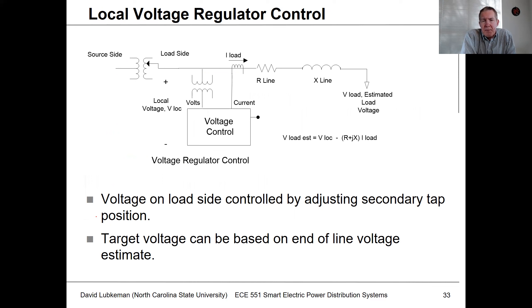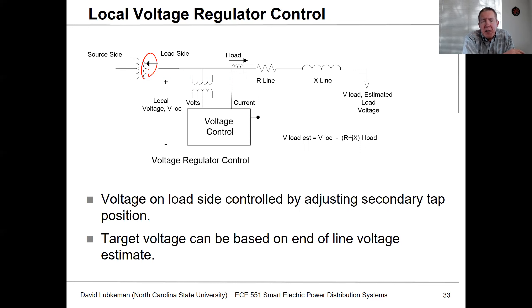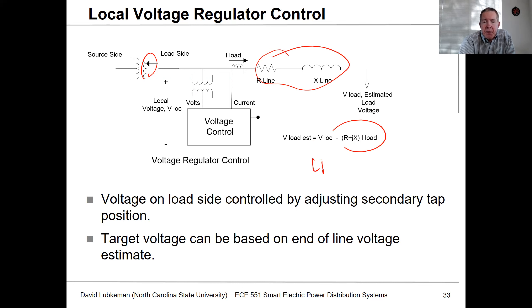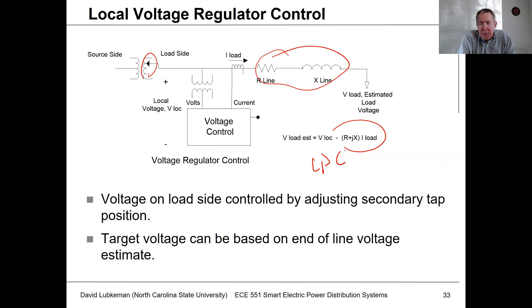Comparing this with line voltage regulators, the line voltage regulator has more resolution in terms of taps — about five-eighths percent resolution per tap. If you really wanted to fine-tune voltage control, a line regulator would be the way to go. If it's placed upstream of a load separated by line resistance, you can also implement line drop compensation (LDC). You can get better voltage resolution with a line regulator, but the problem is cost — it's going to cost maybe 10 times more than just putting capacitor banks out there.